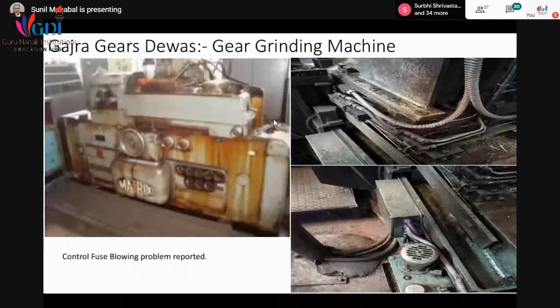So one person shouted, I saw smoke coming out from here. Then we disconnected all the 20-25 conduits going and removed the conduit, and then once again started the machine with the same fuse. Then we saw the smoke coming from one wire. It had already blackened, and we replaced that wire, and beside that wire it had damaged 2 more wires. So those also we replaced.